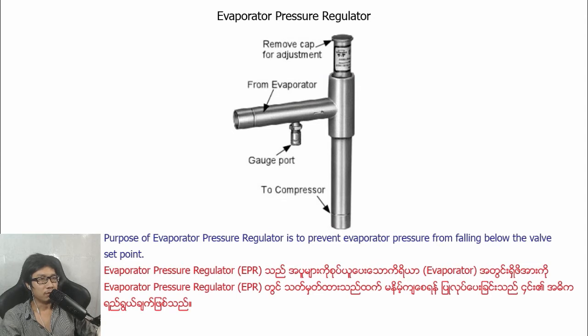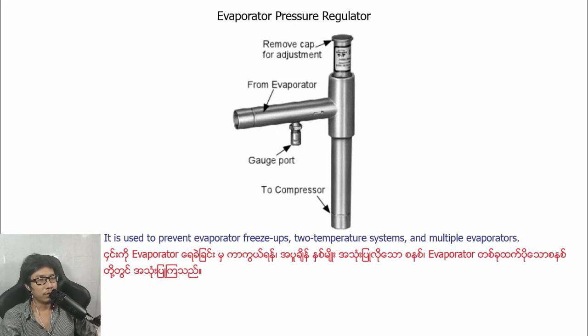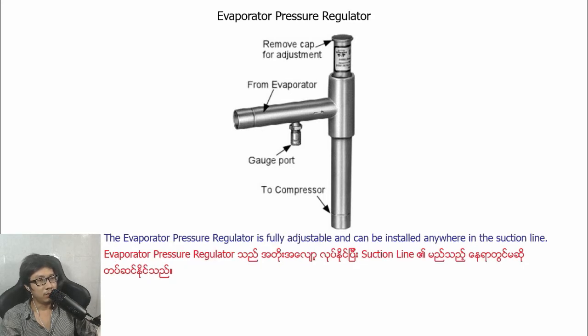Evaporator pressure regulator. The purpose of the evaporator pressure regulator is to prevent evaporator pressure from falling below the valve set point. It is used to prevent evaporator freeze-up in two-temperature systems and multiple evaporator systems. The evaporator pressure regulator is fully adjustable and can be installed anywhere in the suction line.